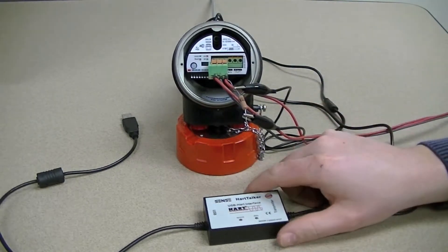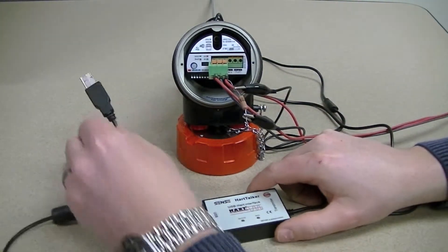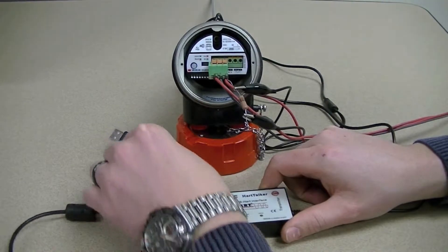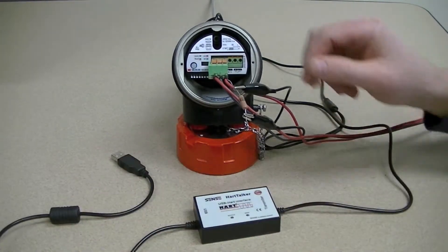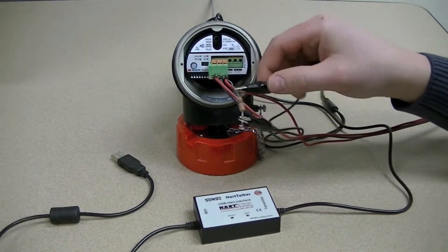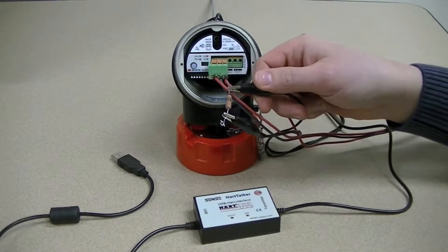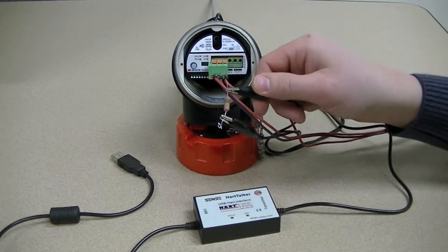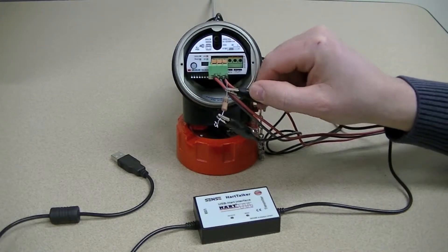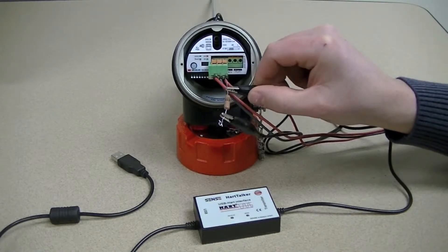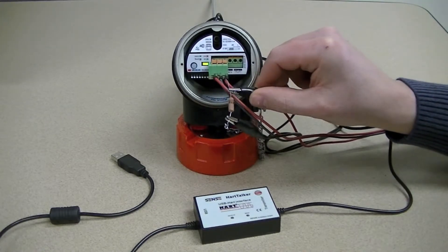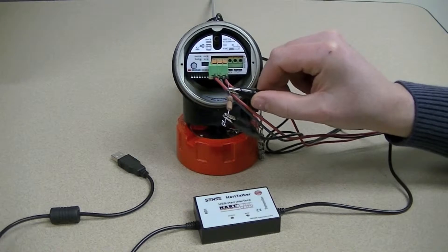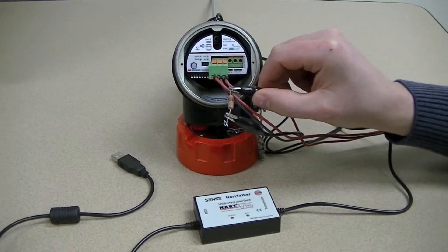The HART modem simply plugs into the PC's USB interface and then we select the alligator clamps and place them on either side of the 250 ohm resistor. The 250 ohm resistor will be positioned in the 4 to 20 milliamp positive output terminal.